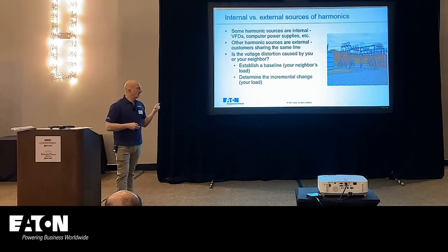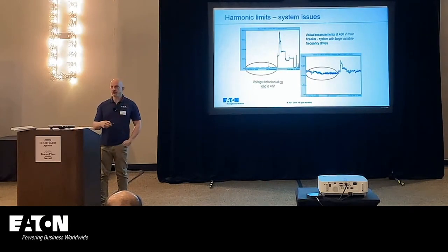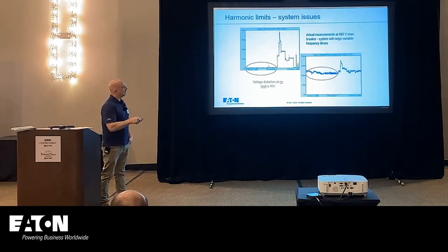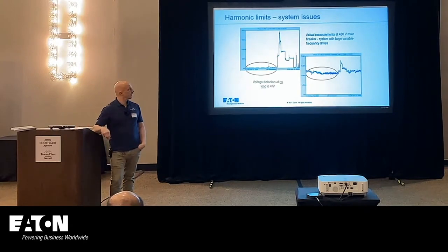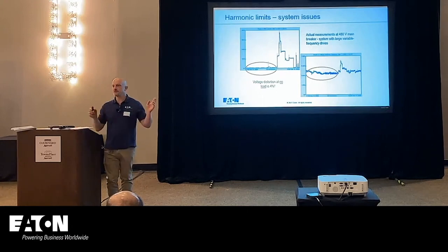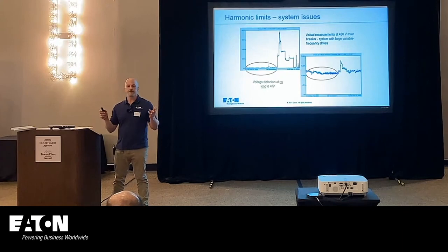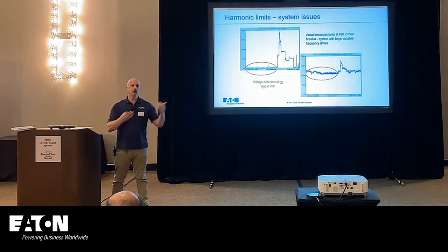All right? But sometimes you have to look at the data. In this case, remember we said current distortion causes voltage distortion? Right now, my plant's shut down. I have no load, but I have 4% voltage distortion. So what does that tell you? Where's that coming from? It's coming from the source. It's coming from maybe somewhere else, the neighbors. Maybe they're creating the voltage distortion, because just because I go from 4% to say 5 or 6% doesn't mean I cross this magic threshold and all of a sudden my stuff's going to fall apart. But if the utility comes back to me and says, hey, you've exceeded this limit that we've imposed, well, you should look at, am I causing it or is the neighbor causing it?